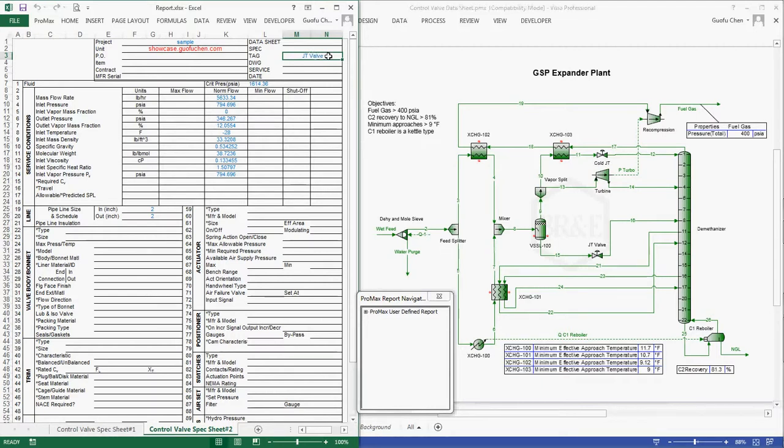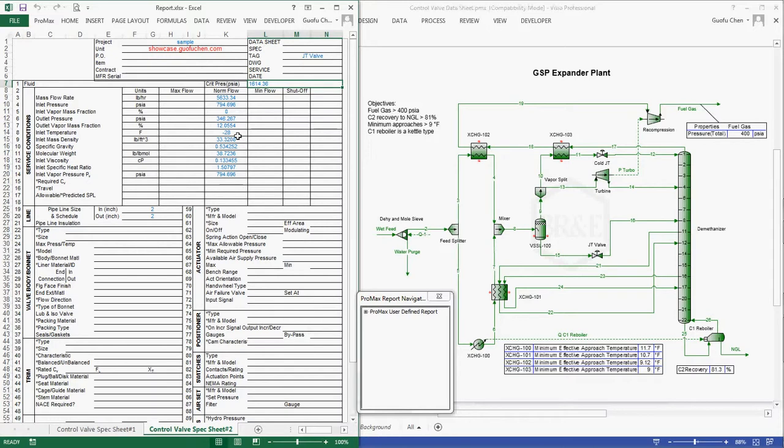It includes the valve tag, the critical pressure, mass flow rate, inlet pressure, temperature, and all the other physical properties necessary to size the control valve. And if the pipe diameter is calculated in the PROMAX simulation file, it will be reported here as well.